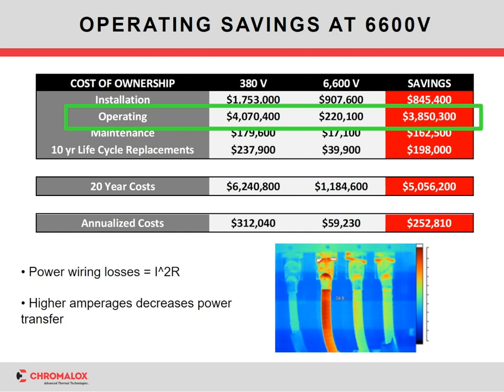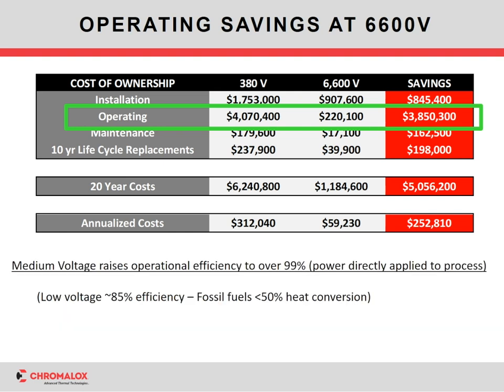And again, that comes down to the amperage that runs through the wire. So in traditional wires, you can calculate the power loss through the I squared R. Again, that's the amperage squared times the resistance of the wire. So in a low voltage system, higher amperage is going to decrease how much power is actually transferred to the process itself. When we look at a medium voltage system, it actually raises the operating efficiency to over 99%. And again, that's measuring the power that's directly applied to the process. If we look at a low voltage system, because of that amperage loss, it's closer to 85% efficiency.